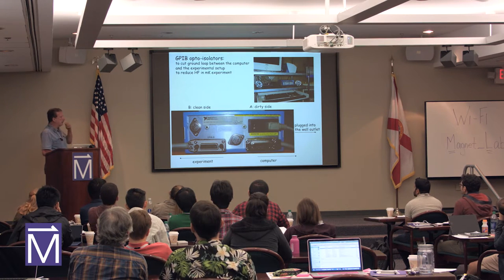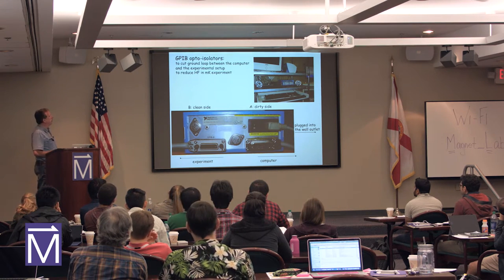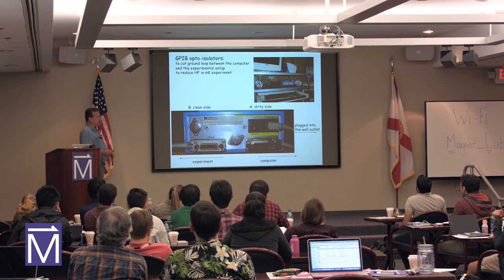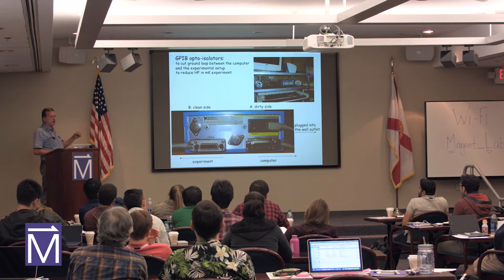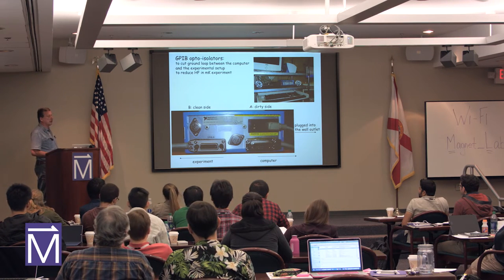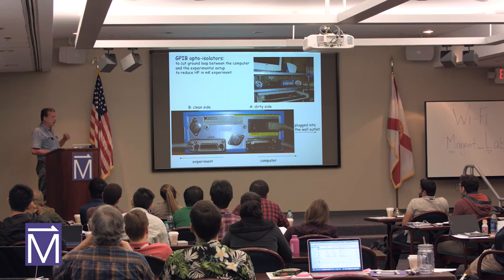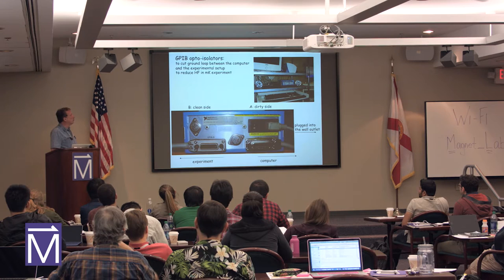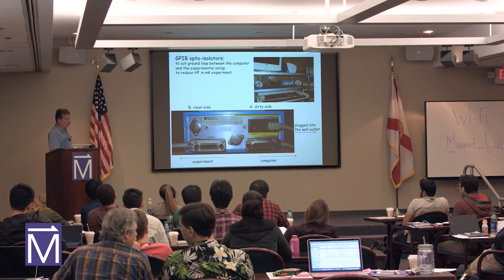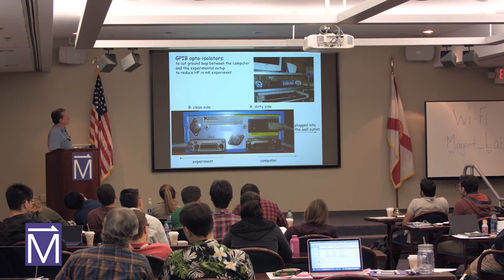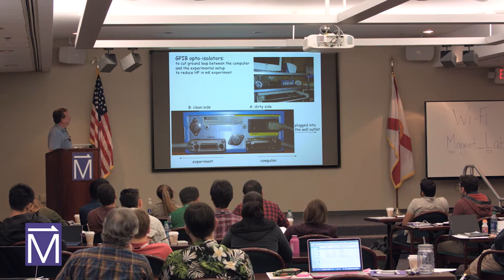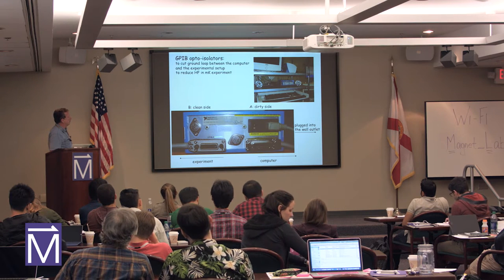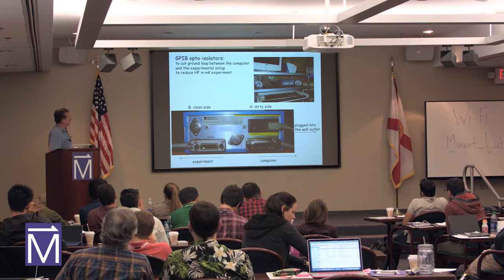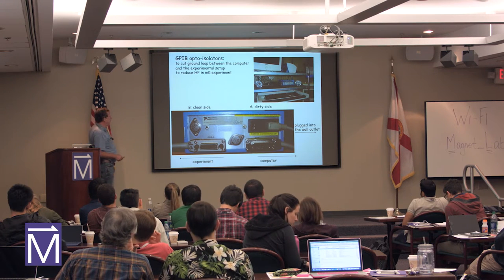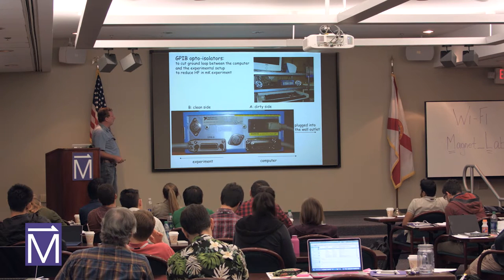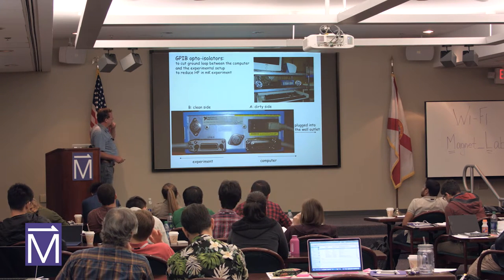As you know, the GPIB cable carries ground. So if we have a computer and our setup, we don't want the computer to be plugged into the same place as our measuring setup, because the computer contains a lot of high frequencies which are not good for our measurement at low temperatures. So to resolve this problem, we use those old GPIB isolators which optically connect input to output. And so there is no ground connection, provided that you connect them properly.